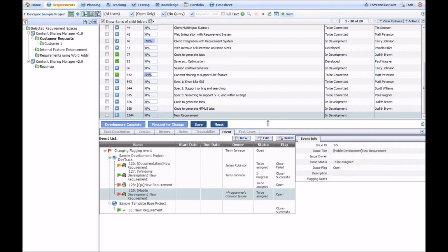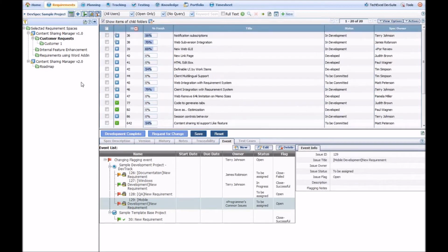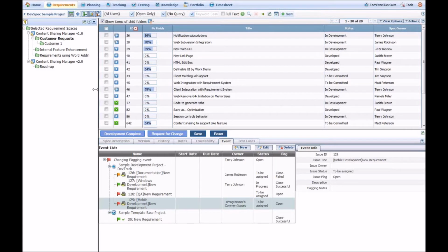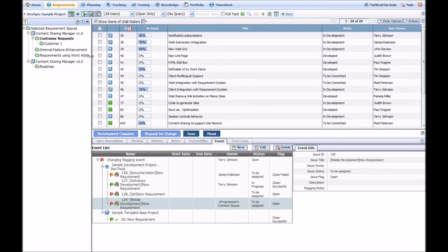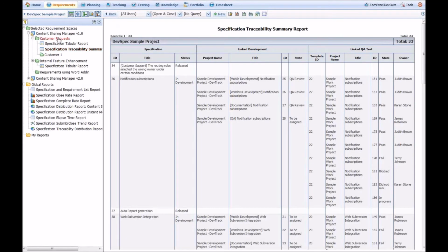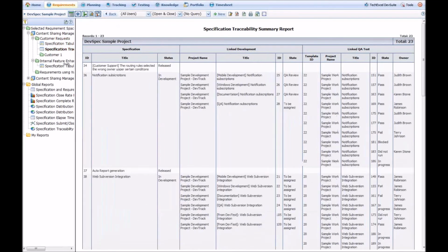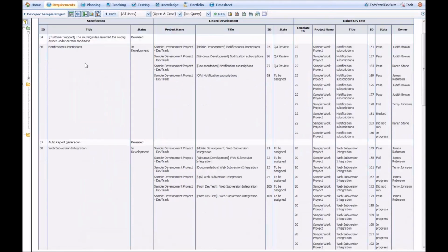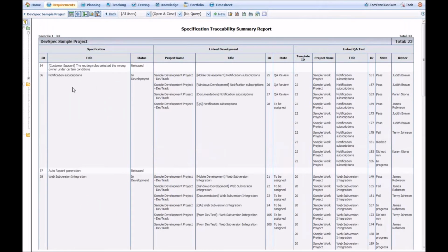The last piece, as part of the DevSuite or as part of the complete verification and validation, is the full traceability report, which is also one of the most important aspects in medical device development compliance. So you simply choose to create a traceability report for one of these requirements. Let me just close this so that I have a full view here. So this is the traceability report once you have all your requirements defined.